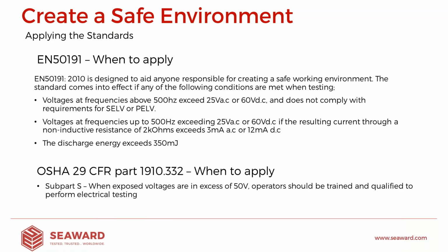So EN 50191 is specifically designed to aid those who need to create a safe working environment when hazardous voltages are potentially being worked on. They make a number of statements that govern when we should look to employ the guidance within EN 50191, and I'm going to talk to you about one specific one now. You'll see it's the middle one: voltages at frequencies up to 500 Hertz, exceeding 25 volts AC or 60 volts DC, if the resulting current through a non-inductive resistance of 2000 ohms exceeds 3 milliamps AC or 12 milliamps DC.